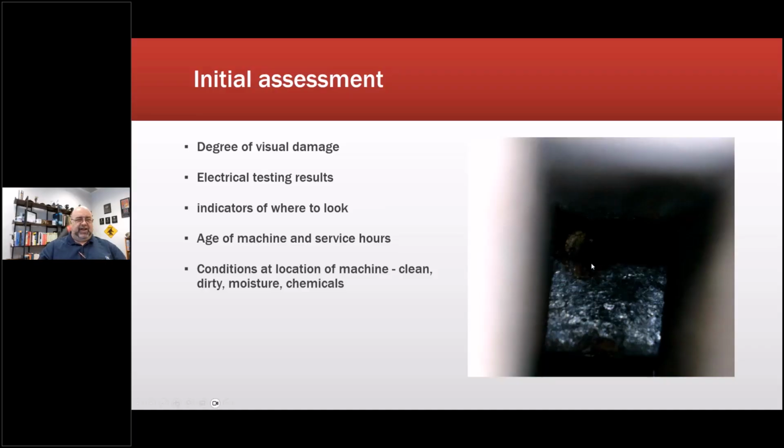That's a mechanical failure. And I went to put down my stuff, and sitting on the desk, because they had said there was a failure and that they would just send me the records. And I go, no, I need to see it. This is an expensive repair for taxpayers. So I go out there, and sitting on the winder's table was a screwdriver with a little bit of this insulation still on the tip. So they had physically damaged the winding. So that made it into a report.